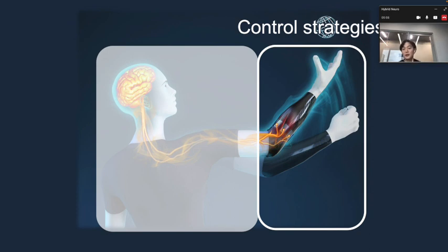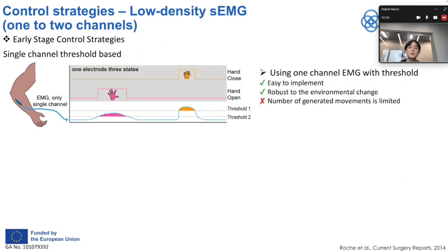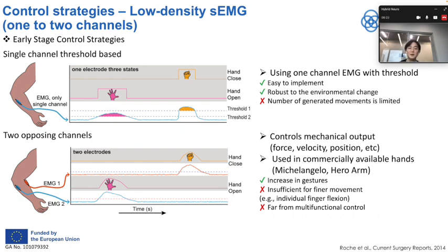Then we will move on to the control strategies, starting from the low-density EMG paradigm. This figure represents early-stage control strategies, which use only one EMG channel with a threshold to control different gestures — very easy to use and robust, but the number of gestures it can produce is limited. The next paradigm uses two EMG channels, where the agonist muscle represents one gesture and the antagonist muscle represents another. This is better than a single channel but still far from multifunctional control.